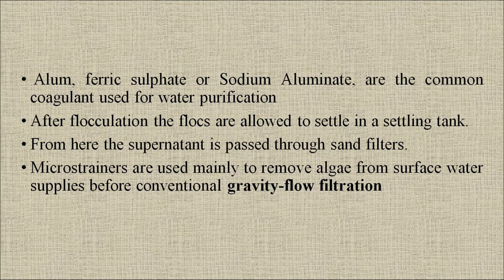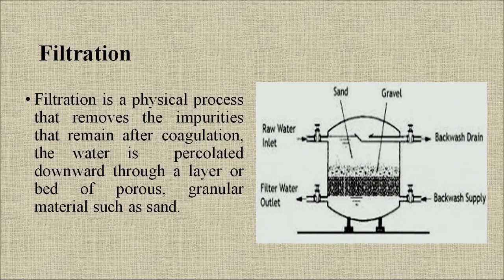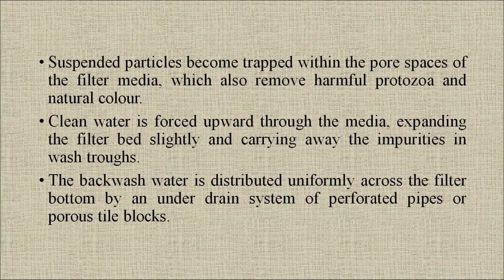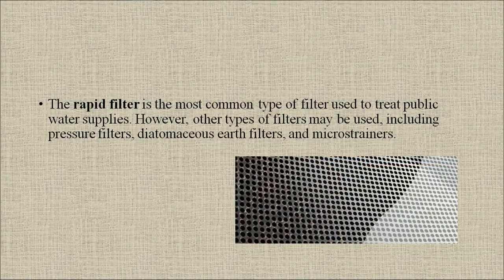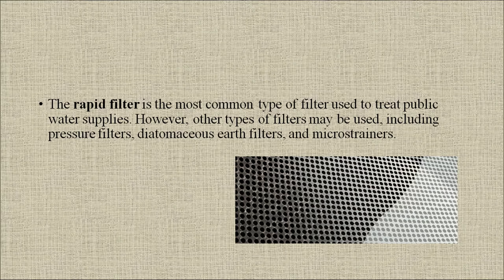Micro strainers are used mainly to remove algae from surface water supplies before conventional gravity flow filtration. Filtration is a physical process that removes impurities remaining after coagulation. The water is percolated down through a layer of porous granular material such as sand. Suspended particles become trapped within the pore spaces of the filter media, which also remove harmful protozoa and natural color. The rapid filter is the most common type used to treat public water supplies; other types include pressure filters, diatomaceous earth filters and micro strainers.